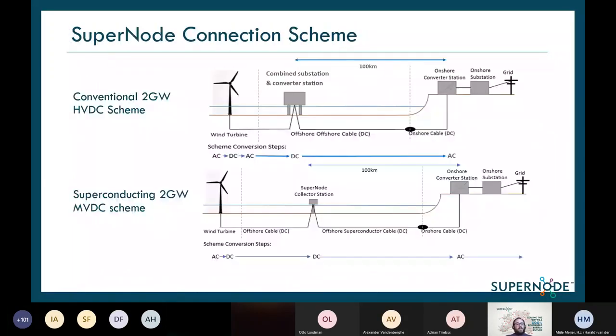The benefits come through in the voltage levels. At the top is a conventional 2 gigawatt scheme, as seen in some wind series platforms in the German North Sea, where wind farms connect straight into a joint substation and converter station before being transported back to land using conventional DC cables. For a superconducting scheme, turbines could instead operate in a DC array format, connecting into a single offshore bus bar where voltage stays at 100 kV but current levels increase, before transport back to land on a single pair of cables. This lets superconductors shrink the offshore platform size drastically.